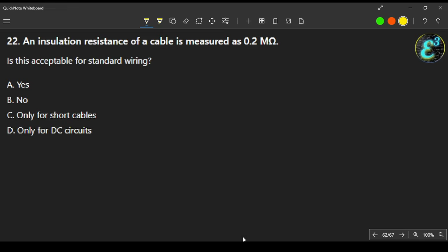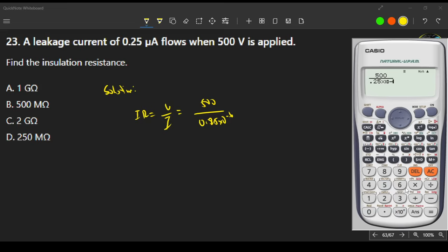Next, a leakage current of 0.25 microampere flows when 500 volts is applied. Find the insulation resistance. Solution: IR equals V over I. Substituting, we get 500 volts divided by 0.25 times 10 to the power of negative 6. That gives us 2 times 10 to the power of 9 ohms, or 2 gigaohms, which is letter C.